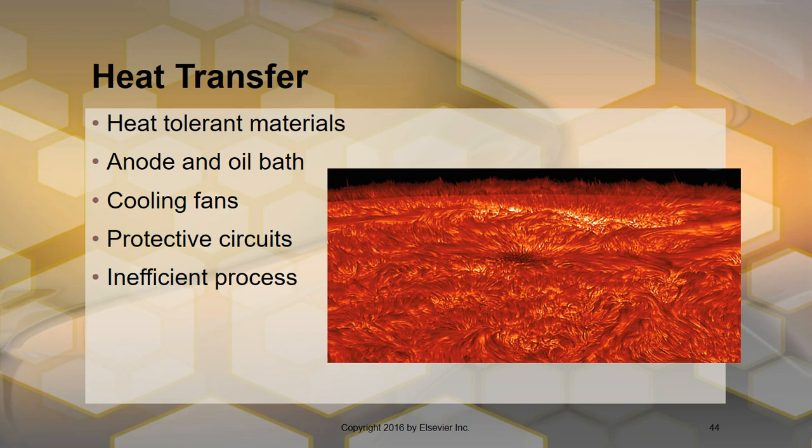There were times in the past where you worked with a single circuit X-ray and it did not have a phased generator, and so if you took a chest and a flat and erect abdomen, you may have to actually let the tube cool down for about 10-15 minutes before you can do another X-ray. We don't have it that bad now, but we need to understand that it could if we were to use unsafe practices.